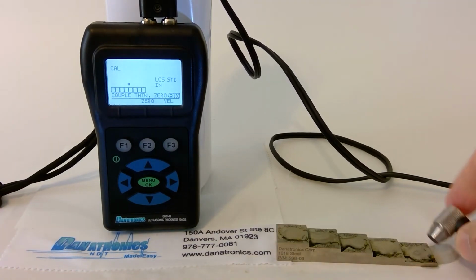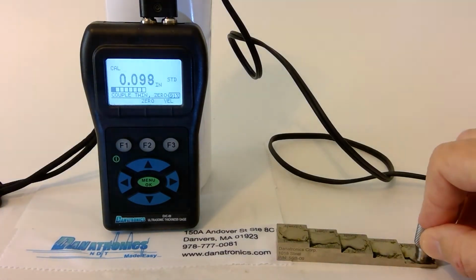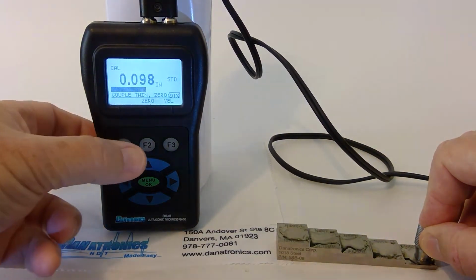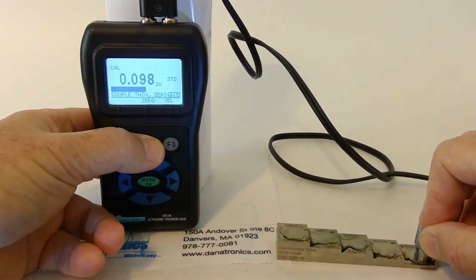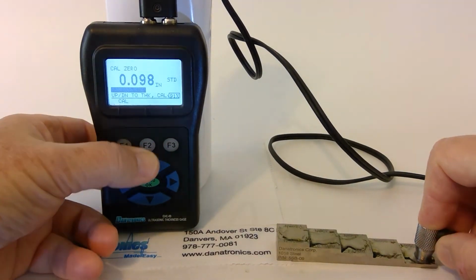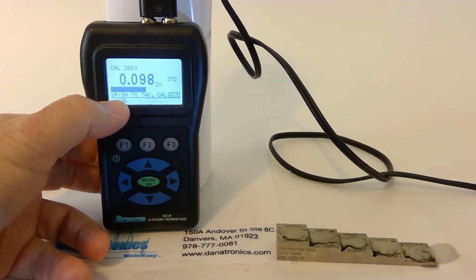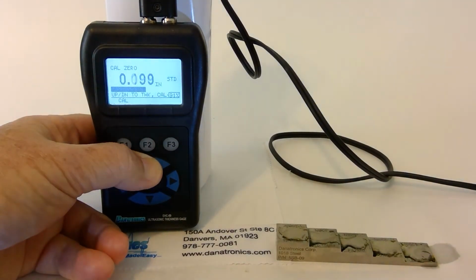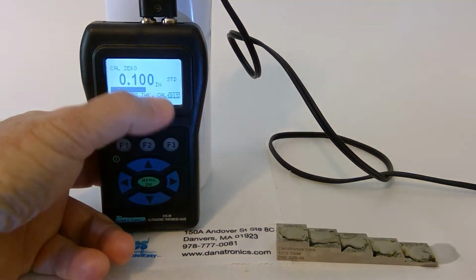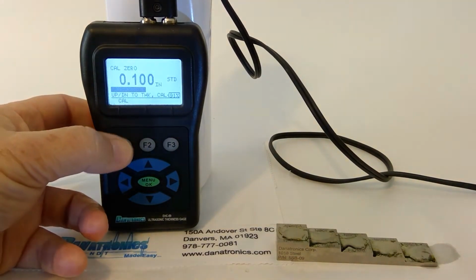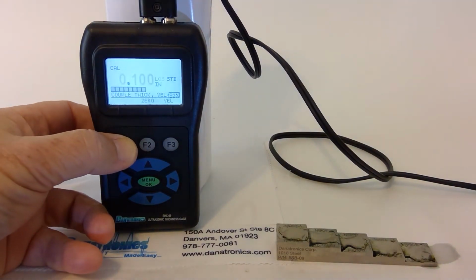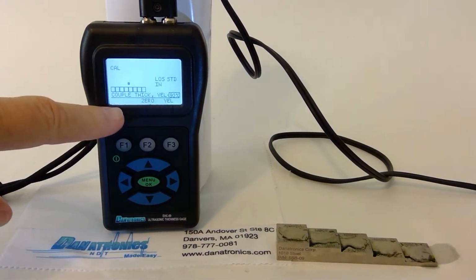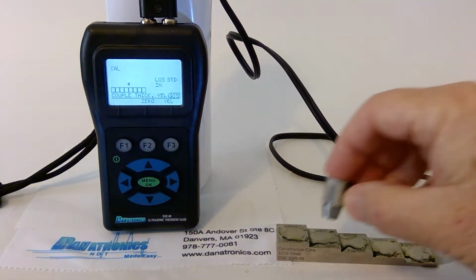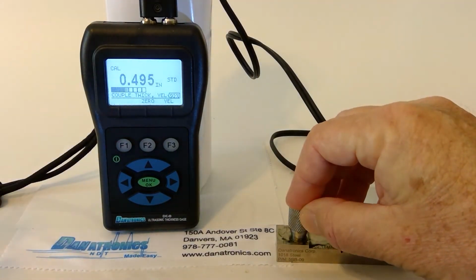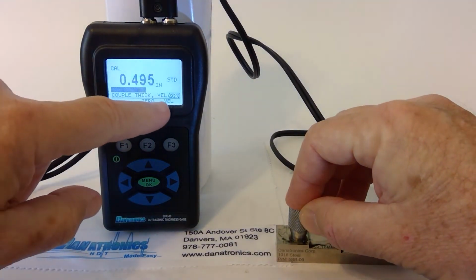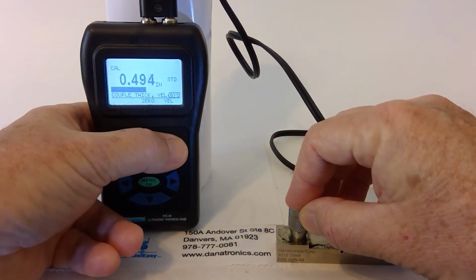We couple thin on the 100 thousandth side of the block. Then we press 0 under the F2 button. Using the up or down arrow keys, we adjust to come to 100 thousandths. Then we press the cal or F1 button. Next, it's asking us to couple thick. Then press velocity, the F3 button.